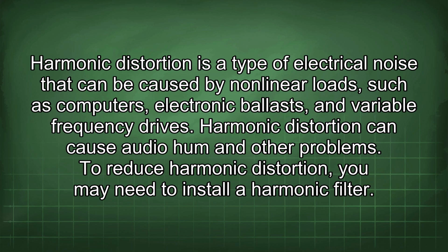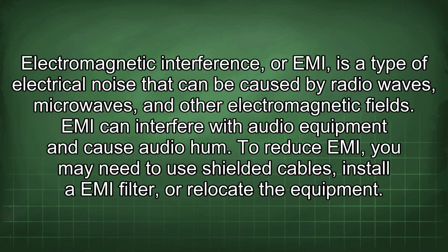Harmonic distortion is a type of electrical noise that can be caused by nonlinear loads such as computers, electronic ballasts, and variable frequency drives. Harmonic distortion can cause audio hum and other problems. To reduce harmonic distortion, you may need to install a harmonic filter. Electromagnetic interference, or EMI, is a type of electrical noise that can be caused by radio waves, microwaves, and other electromagnetic fields. EMI can interfere with audio equipment and cause audio hum. To reduce EMI, you may need to use shielded cables, install an EMI filter, or relocate the equipment.